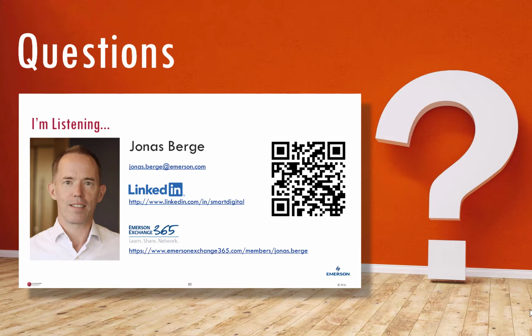And one question is, has NAMUR tested WirelessHART? The answer is yes. They tested WirelessHART back in 2009. It was actually tested by BASF in their Ludwigshafen plant. Can I mix update times in the same network? Yes, you can. You can have 1 second or a few seconds, and 1 minute or a few minutes, or 1 hour, all in the same network at the same time, in a mix of devices.